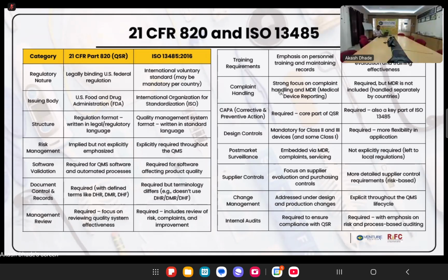Then the complaint handling procedure. This was a mandatory part of 21 CFR 820. Any medical device that is going to be commercialized in the US is mandatorily asked for medical device reporting. Whether your device is class 1, class 2, or class 3, this MDR, the medical device reporting requirement, was an inbuilt part of QSR. Whereas in ISO 13485, it was not explicitly mentioned that you should have medical device reporting, but it was asking you to do market surveillance or continuous monitoring. So you may have SOPs for market surveillance, but medical device reporting is an essential part of QSR. That was a major difference between QSR and ISO 13485.